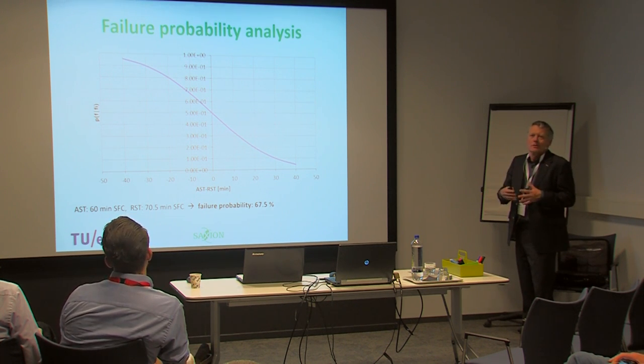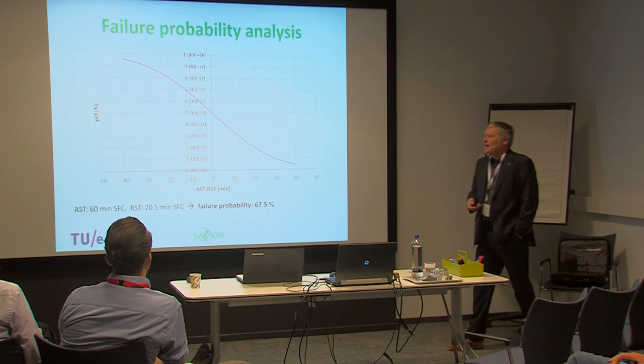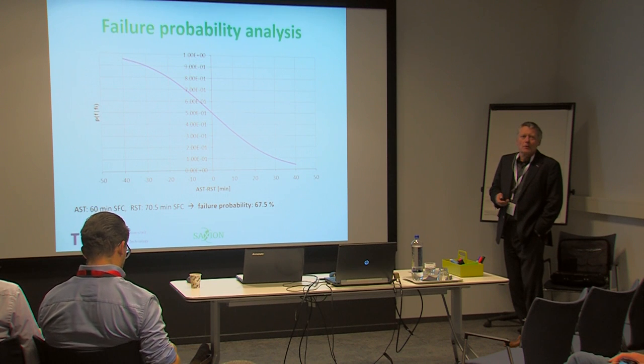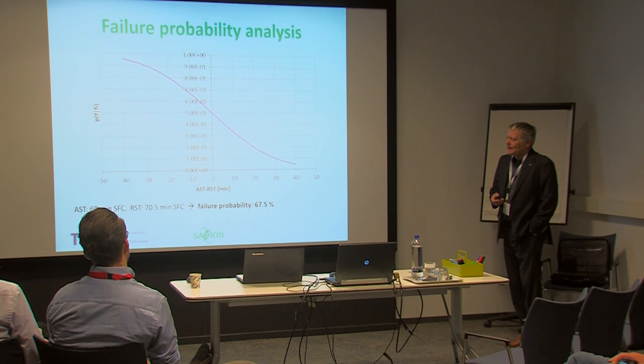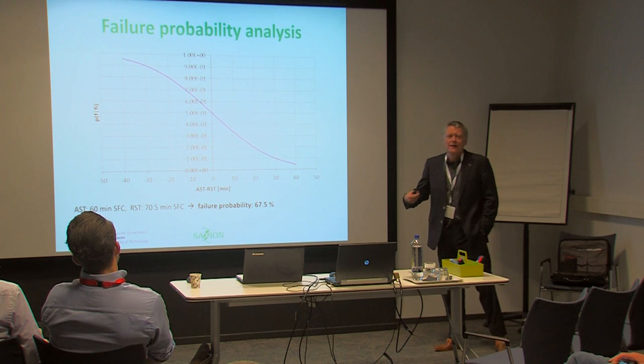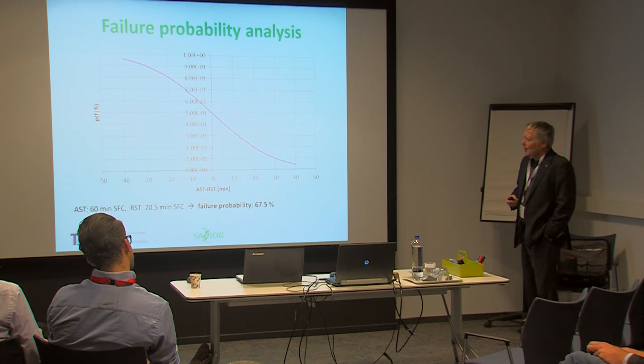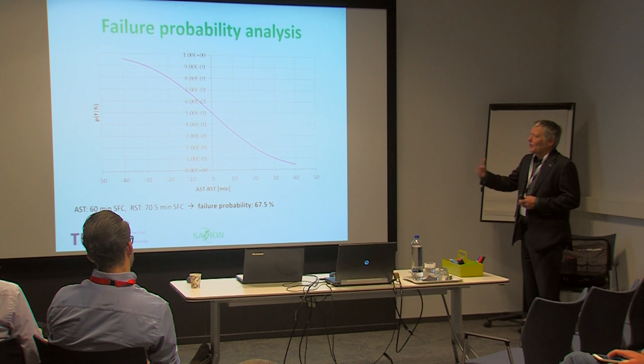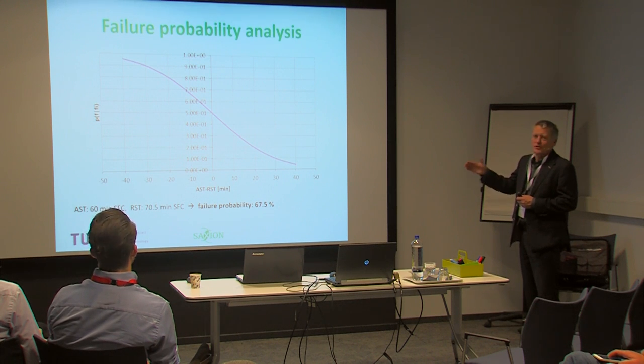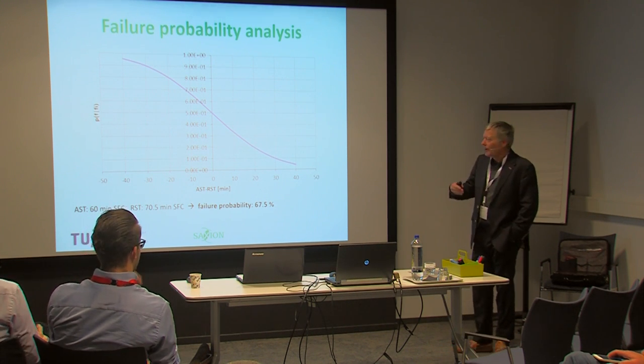Compared to this morning's example with a lower fire load where 30 minutes sufficed, here you see it makes sense to really calculate the thermal load and to assign different fire resistance ratings to separation constructions depending on the thermal load and required reliability. Here also comes the Saxion students' project, because this is only one-dimensional. We need to add the failure probabilities of adjoining constructions: adjoining walls, facades, floors, roofs, as well as ducts and doors going through the wall.